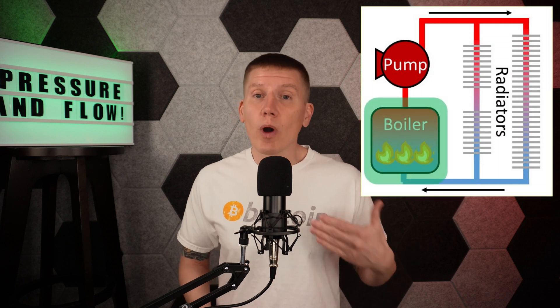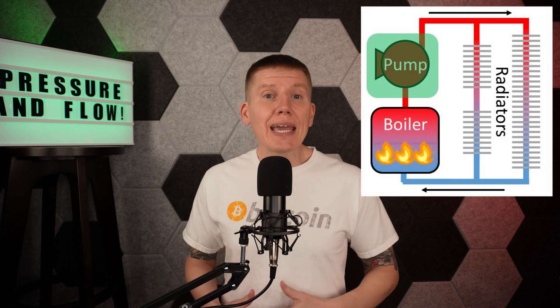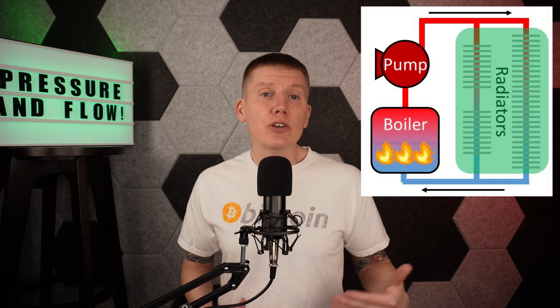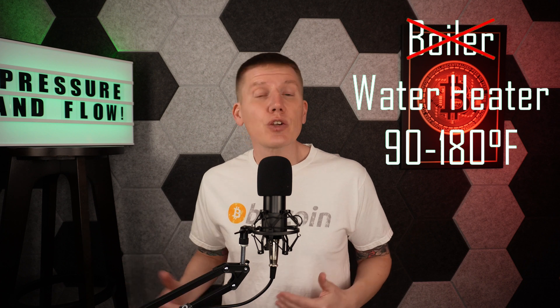Well, it's a heating system consisting of a boiler, which heats a water-based coolant. That coolant is then pumped around your house using a circulator pump, and it passes through radiators to heat rooms, floors, or whatever else you want to heat up. Now, the term boiler is a bit of a misnomer. In early hydronic systems, water was boiled and steam flowed in the piping around your house, and there are still steam-based systems out there. But most home hydronic systems nowadays do not boil water — they just heat it up to somewhere between 90 and 180 degrees Fahrenheit.